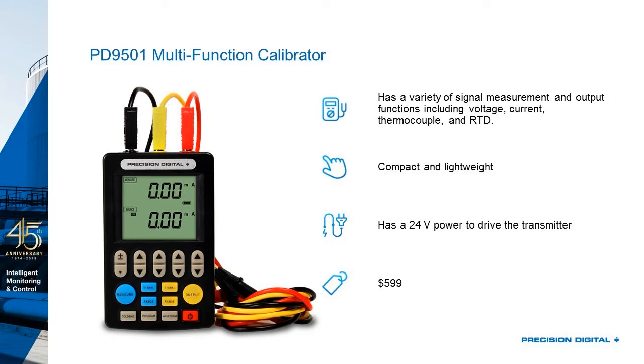It can charge up via USB cable, and you can just take it out in the field wherever you need it to go. One great thing about this is it includes the 24-volt power needed to drive a transmitter. So if you want to check if your transmitter is working, we can actually source the power needed to bring that 4 to 20 back into this handheld unit. This starts at $600, or $599, so it's a great alternative to some much more expensive products similar to it in the field right now.